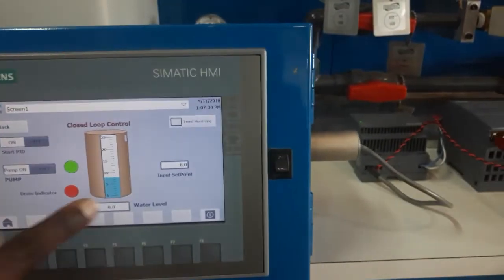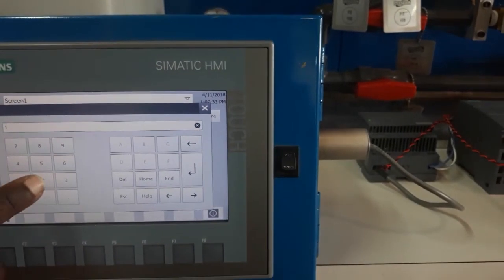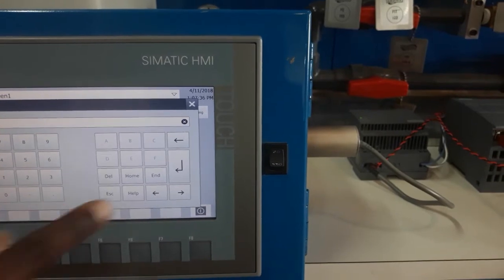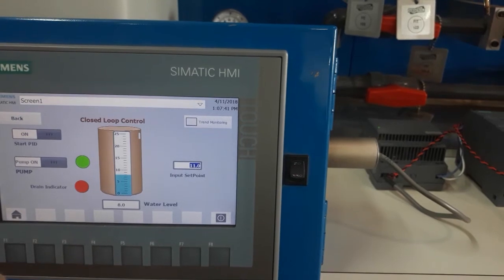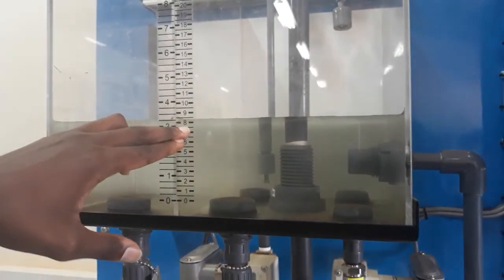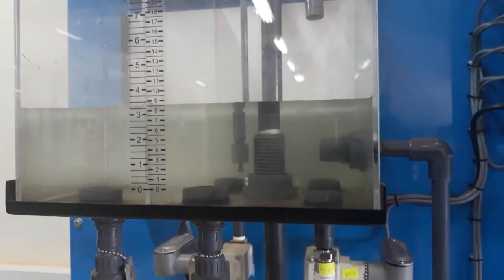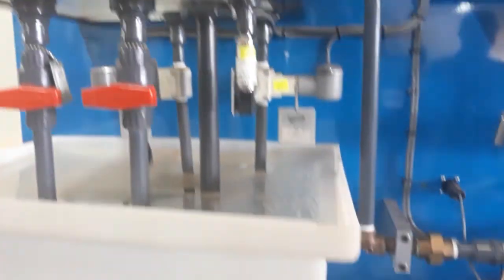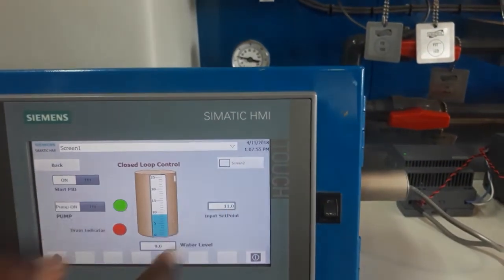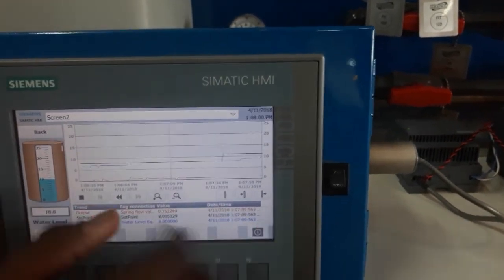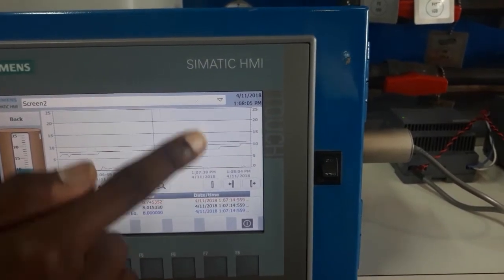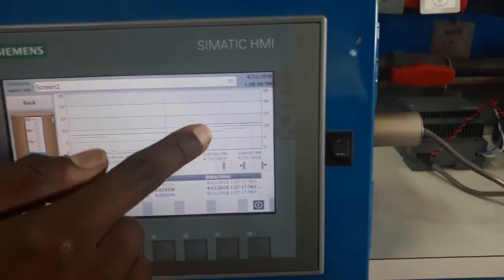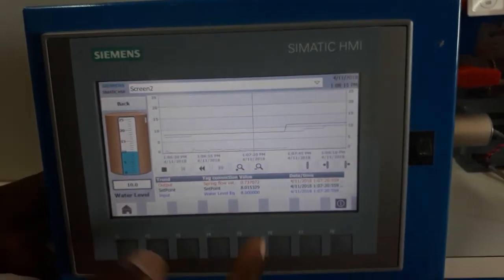Then I can change the setpoint from 8 to 12, or to 11. Then the system realizes that the setpoint has been raised to 11, and it raises the water level from 8 to 11, as it tries to maintain the water level at the new setpoint. You can go ahead and look at the trend. From the trend, you can see the black trend, which is the setpoint, has been shifted from 8 to 11, and the blue trend, which is the water level, is trying to catch up with the black trend.